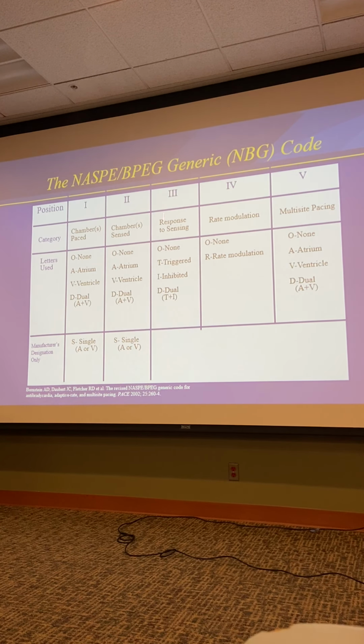And then there are a lot of smarts and artificial intelligence that are being put in these devices to help it make programming choices on its own. This is well beyond what we're going to talk about today, but the idea of refractory periods is critical to how the pacemaker responds. Every time there's an atrial event, whether it's sensing a P wave or pacing the atrium, and every time there's a ventricular event, either sensing an R wave or pacing the ventricle, both the atrial and ventricular circuits are going to go deaf for a short period of time, so that they don't get fooled by the noises and electrical signals that happen right around the time of pacing.